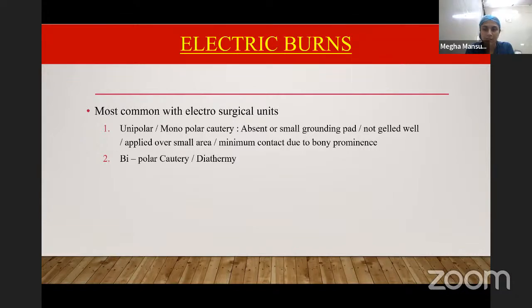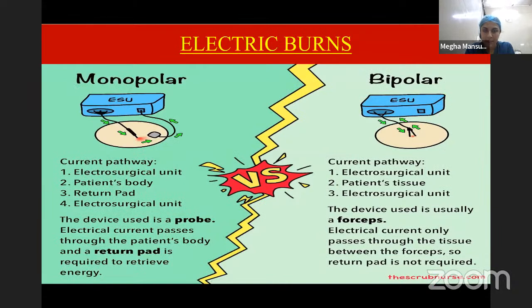Now we need to link current pathways in a monopolar and a bipolar cautery. In a monopolar cautery, the current passes from the electrosurgical unit to the patient's body to the return pad, which is placed separately on a large surface area part of the skin, and back to the electrosurgical unit. We use a device which is a probe, and current passes from the probe to the return pad and then back to the electrosurgical unit. However, in a bipolar cautery, the device used is a forceps, and the current passes from the electrosurgical unit to the patient's tissue from one end of the forceps back to the other end of the forceps and then back to the electrosurgical unit.